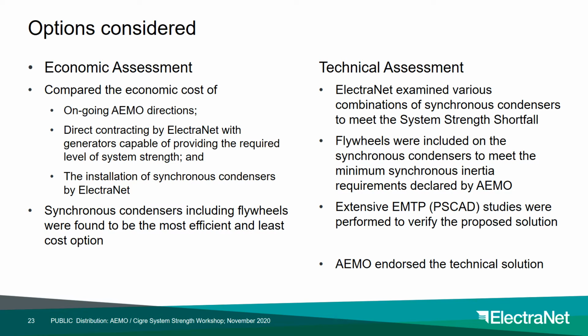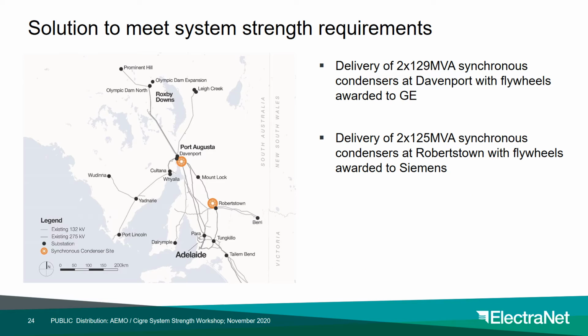The declared shortfall listed minimum short circuit levels within South Australia as the requirement to be achieved. However, these short circuit levels are only a proxy for system strength, and therefore extensive EMTP studies were undertaken to verify that the proposed solution met the technical requirements. Following extensive studies, AEMO endorsed the technical solution proposed by Electranet. Electranet's proposed solution was to install synchronous condensers at each of the Davenport and Robertstown substations in the Mid-North region of South Australia. These sites were chosen in particular because of the close proximity to inverter-based resources within the area and the effectiveness of installing synchronous condensers at these sites as shown in the system studies.